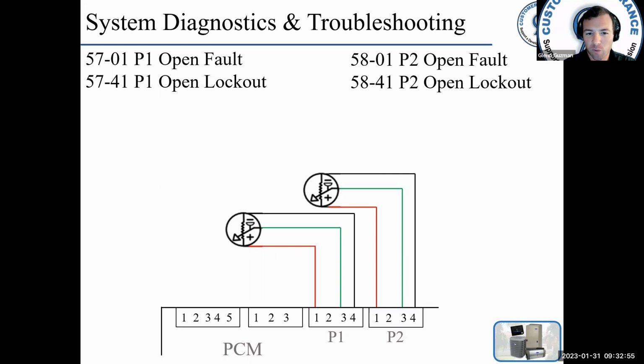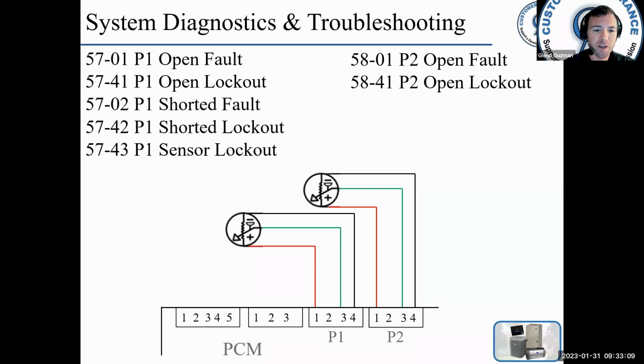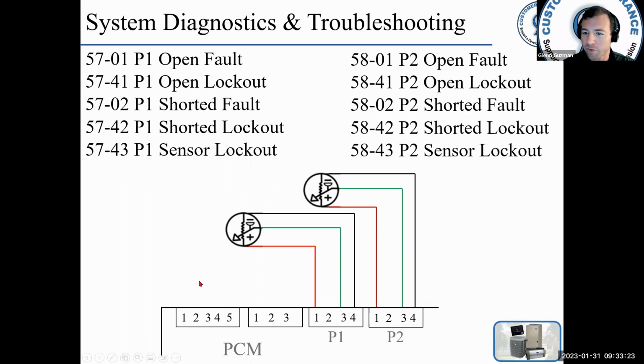5701 and 5741. That's a P1 open or open lockout. 5801 is P2 open fault, and 5841 P2 open lockout. 5702 is shorted fault. 5742 P1 shorted lockout. 5743 P1 sensor lockout. And we do have the same 5802, 5842, 5843 for the P2. So several different transducer faults that can occur.